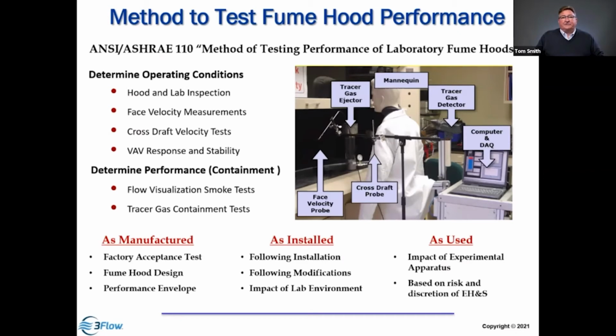And then finally, there's the as-used test. Under the as-used test, we're going to apply the same level of tests as before, except now we're trying to evaluate the impact of operational conditions, how the hood's being used, the influence of the operator in some cases, as well as the experimental apparatus in the hood. That's really up to the discretion of the EH&S, because a lot of times we know the hood's functioning properly, providing a good degree of containment. If it's used within the capabilities and limitations of the hoods, it should provide adequate protection, but sometimes we want to know where it's on the edge.